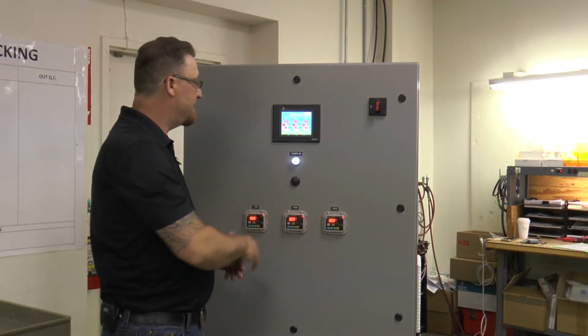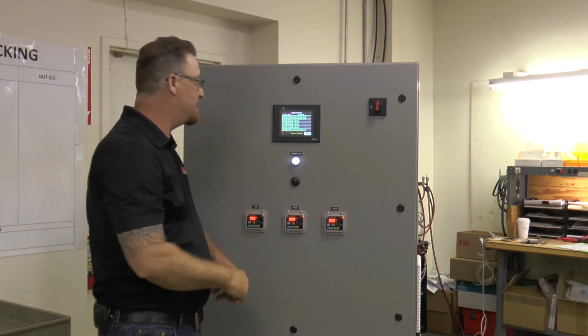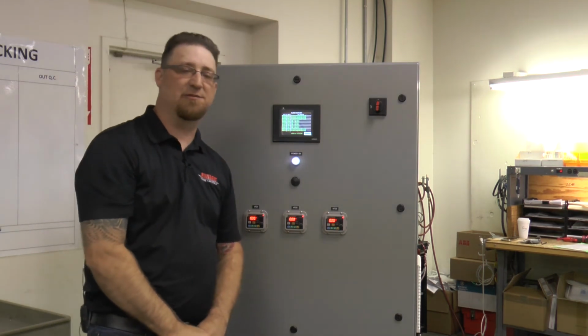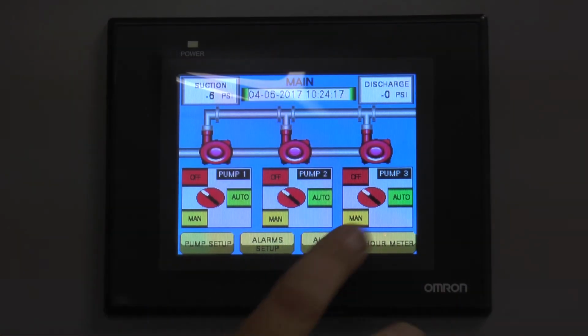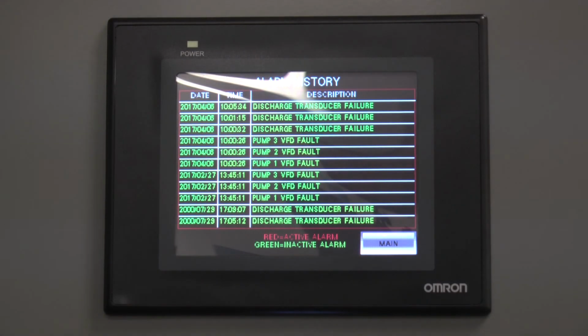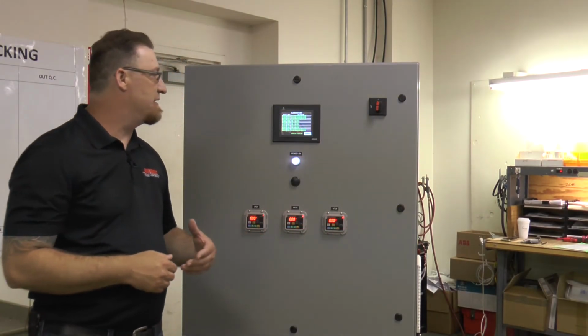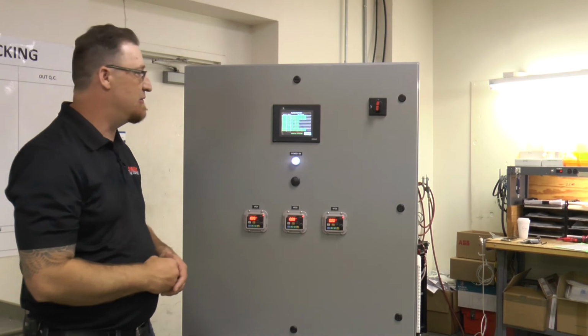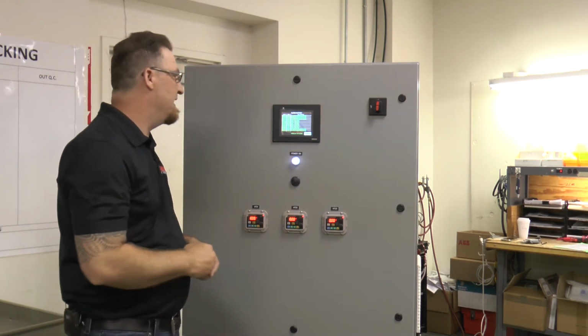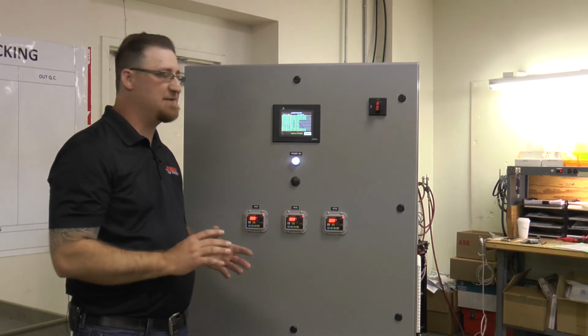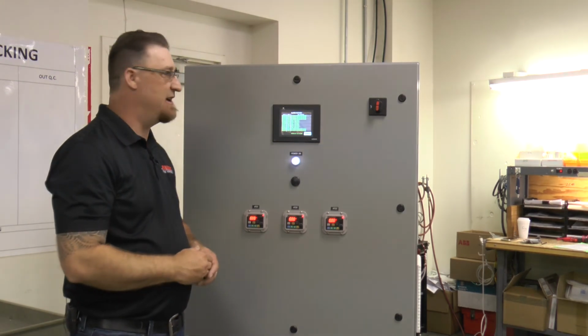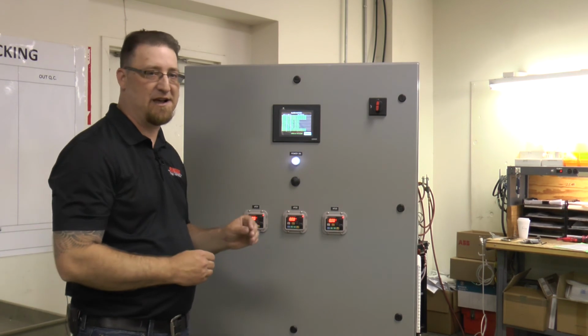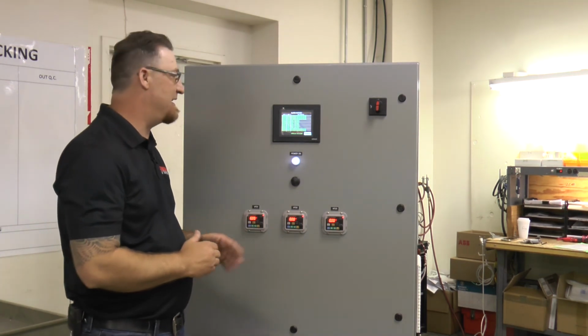We go to our main screen, here we are. We also have an alarms history button. So if you're wondering why you're having an alarm at this moment in time and what's wrong, well, here's our history. So right now, these are in the past. It tells you the date and the time in which you had an alarm. And these alarms can be anything such as the VFD's faulted, or your transducer has failed, or you had high discharge or low discharge. Anything that is in green has been cleared. It's not active at the moment. If it's red, it's active. So you actively have an alarm at that moment in time if it's red.